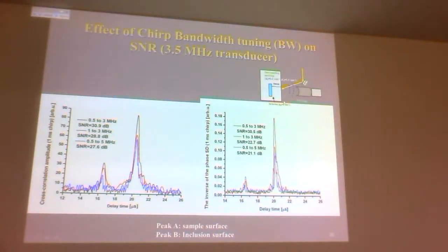So what frequency bandwidth do I use? Again, you're looking at the case here, 0.5 to 3 megahertz. This gives you the maximum. You would not know that, because you could go from 0.5, you could go to 1 to 3 megahertz, but then you get a lower response. Or you could go from 0.5 to 5 megahertz, so you think that you're better, but in fact you're worse off. Let alone the fact that if you increase the frequency response too much, then you have noise coming in, because noise does not care about frequencies. It comes in essentially at all frequencies. So the more open you are, the more noise you're going to get into the system. You really want to be as narrow as possible as far as noise goes. So there is a trade-off here.